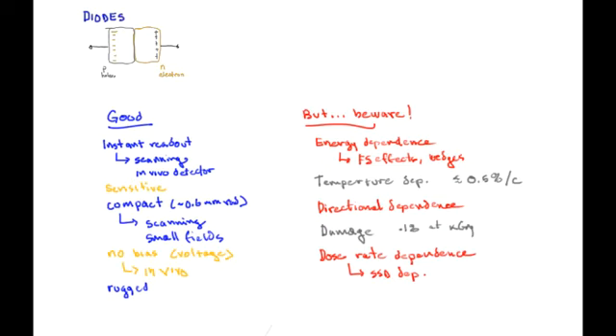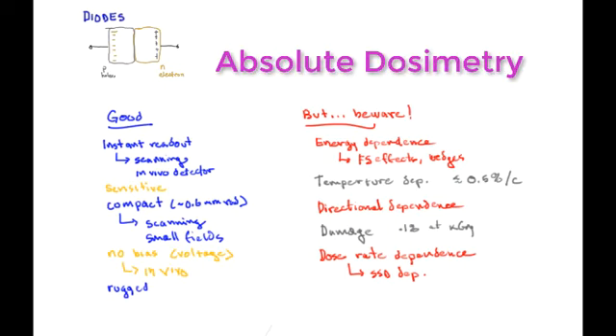Before we leave diodes, I want to mention one last thing about them: they are not used typically for absolute dosimetry. Absolute dosimetry means calibrating your machine, finding out the number of centigray per MU—that's done with an ion chamber as we talked about in the last videos. Diodes are more useful for measuring relative dose, like scanning across a beam getting a profile or scanning up and down in a beam getting a PDD.